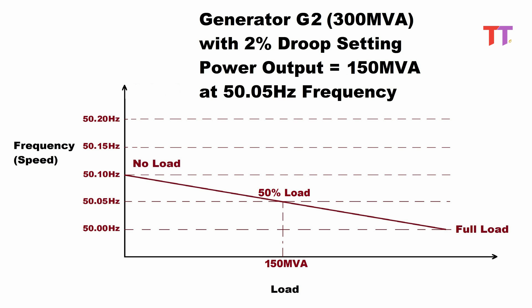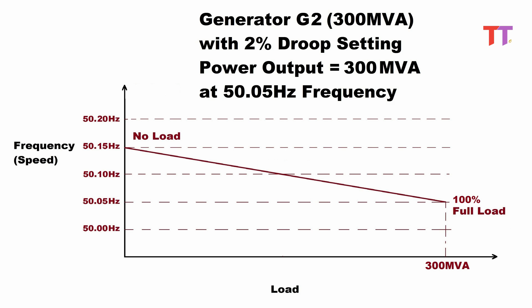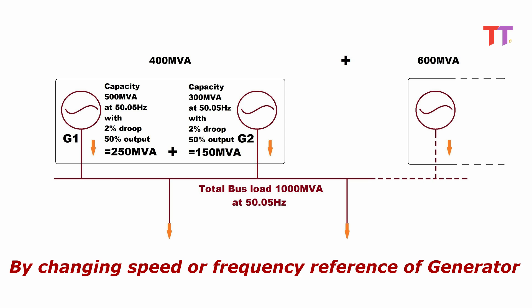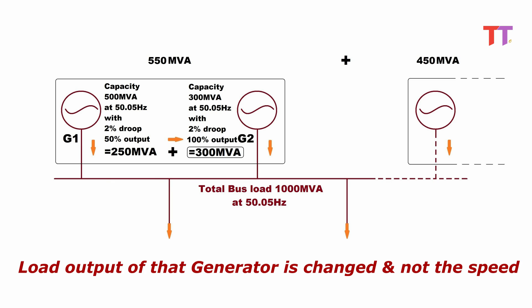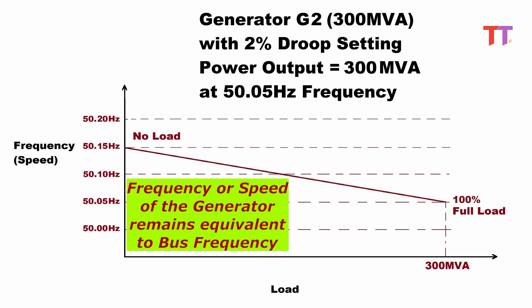In this way, using droop setting, the load of a generator can be controlled by varying the reference speed of the droop. From this we can see that by changing the speed or frequency reference of the generator, the load output of that generator is changed and not the speed. The frequency or speed of the generator remains equivalent to bus frequency.